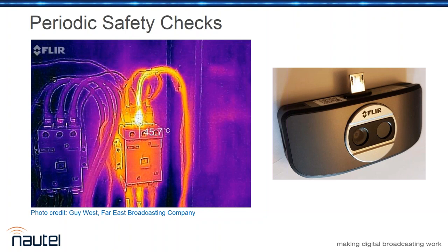One thing to remember, and we'll mention it again later, is that anytime you have a stranded wire in a compression connection, like a circuit breaker, it's going to work loose. The copper in the wire is malleable, it compresses to displace any air left in the connection, and it becomes loose. Once it's loose, it gets hot, and if it gets hot enough, bad things happen. So do a little thermal scan if you walk into a site once every couple of months, scanning the breaker panels. It will show you any hot spots or warm spots. If you see any, take the cover off the panel and scan it again, and you can find exactly where the problems are before they become big situations.